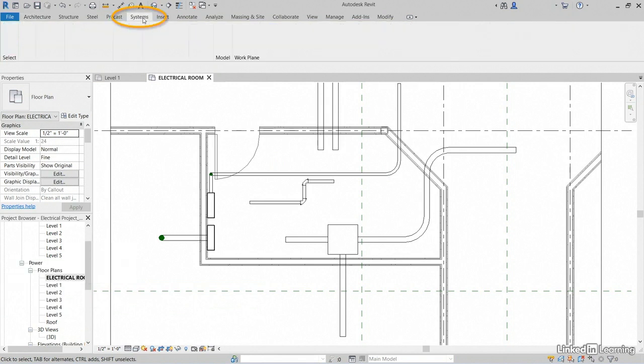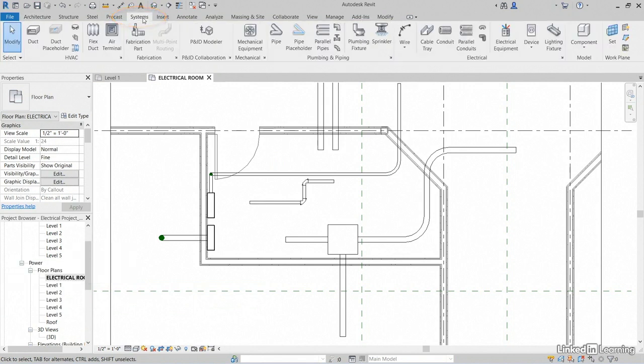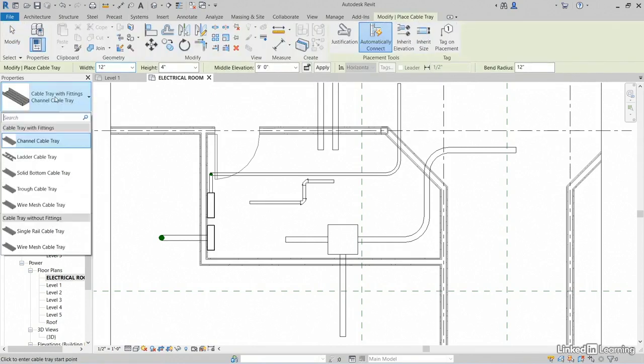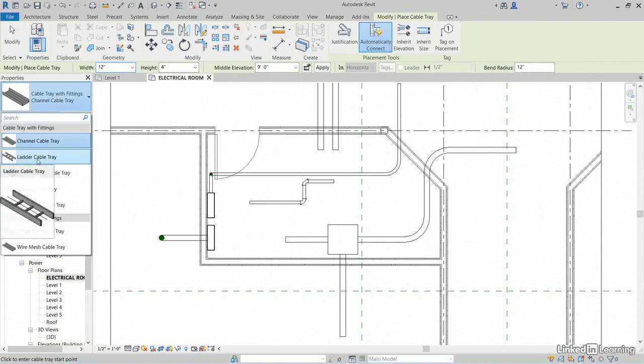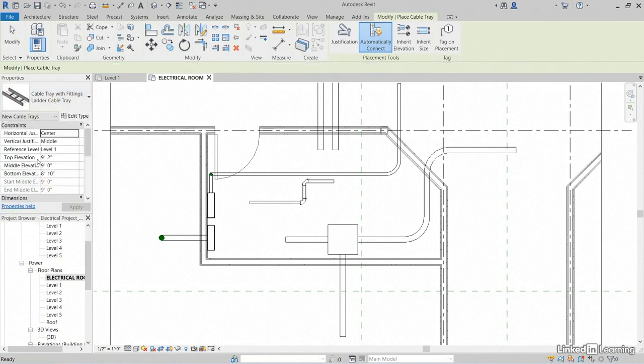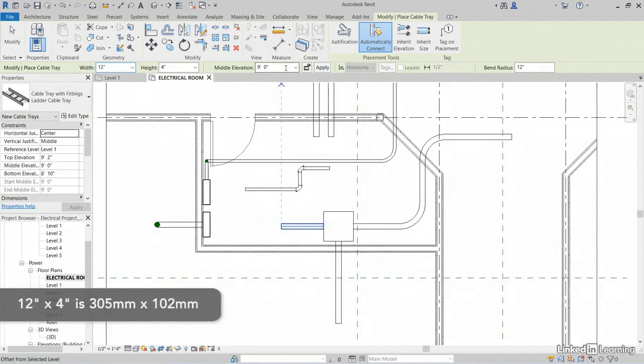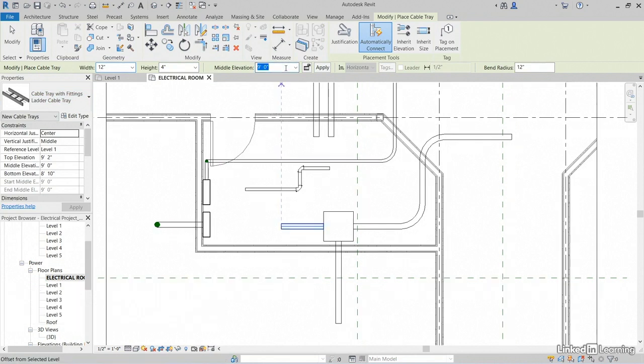Let's go to our Systems tab. On the Electrical panel, let's click Cable Tray. Let's come over to our Type Selector. Click the dropdown. Let's grab Ladder Cable Tray. The width is 12 by 4, or 305 by 102. Let's set our middle elevation to 11 feet, which would be 3353 millimeters.